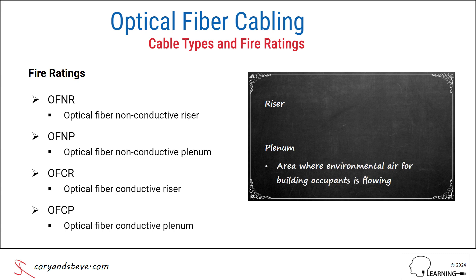Riser and plenum are terms used to identify the intended location of the cable within a building. If the cable is to be placed in an area where environmental air for building occupants is flowing, it must have a plenum rating. For example, the network cables placed horizontally above a suspended ceiling that's used to return warm air to the air conditioning system in an office building would have to be rated plenum, whereas cables placed vertically between floors in the same building would require a riser rating.